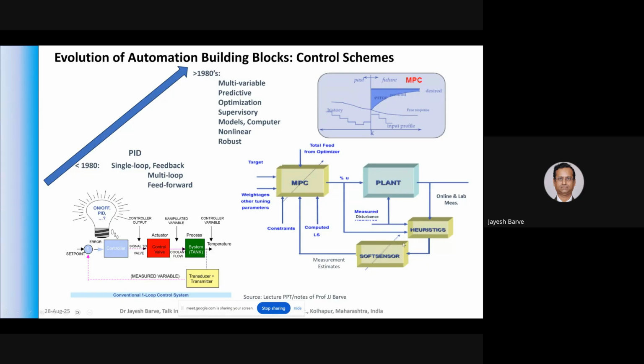Some quality parameters are measured in the lab, and this lab measurement comes every 2, 3, or 4 hours depending on the frequency of measurement. But I need to decide set points every minute and change them minute to minute. So we used a soft sensor based on the model. We had a measurement system—a software controller, a high-end control scheme, which is model predictive control—using the model and optimization algorithm, data from the soft sensor, and tuning parameters of the algorithm itself, to decide the set points.